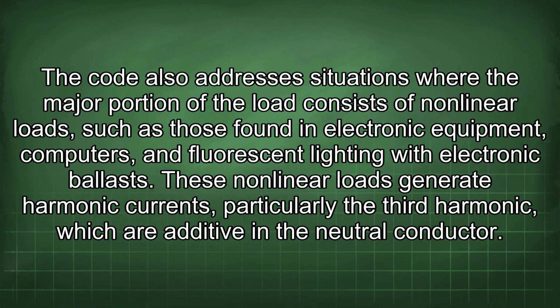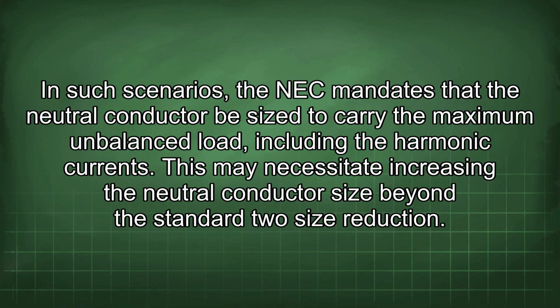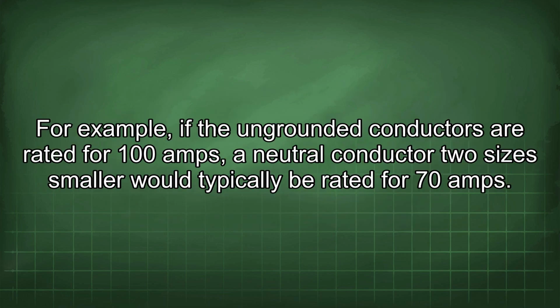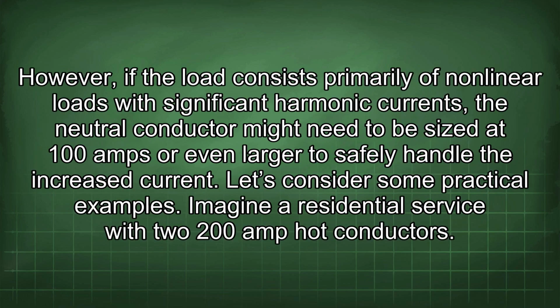found in electronic equipment, computers, and fluorescent lighting with electronic ballasts. These nonlinear loads generate harmonic currents, particularly the third harmonic, which are additive in the neutral conductor. In such scenarios, the NEC mandates that the neutral conductor be sized to carry the maximum unbalanced load, including the harmonic currents. This may necessitate increasing the neutral conductor size beyond the standard 2-size reduction. For example, if the ungrounded conductors are rated for 100 amps, a neutral conductor 2 sizes smaller would typically be rated for 70 amps. However, if the load consists primarily of nonlinear loads with significant harmonic currents, the neutral conductor might need to be sized at 100 amps or even larger to safely handle the increased current.